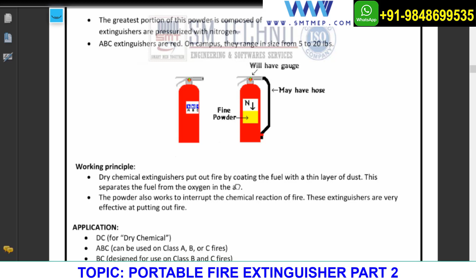Similarly, we have a list of powders, but the greatest portion of this powder is composed of monoammonium phosphate. Monoammonium phosphate with the potassium, with the sulfate, we have different combinations. And for that, in NFPA 10, you can refer to Table number 10. In that you'll find the list of different chemicals with the powder options, with the capacity and standard also. But mostly we'll get the information from the manufacturer too.